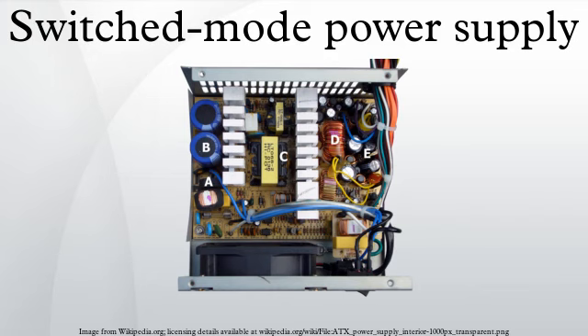The current flowing from line or neutral through a 2000 ohm resistor to any accessible part must, according to IEC 60950, be less than 250 microamps for IT equipment. Applications. Switched mode power supply units in domestic products such as personal computers often have universal inputs, meaning that they can accept power from mains supplies throughout the world, although a manual voltage range switch may be required. Switch mode power supplies can tolerate a wide range of power frequencies and voltages.